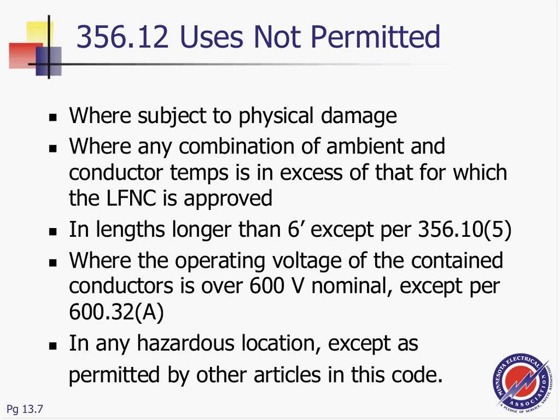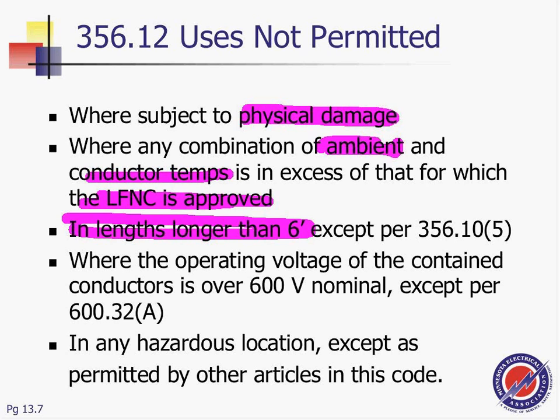Okay, now prohibition. Where can't I use it? Guys, severe physical damage. If you have physical damage, you might as well have rigid metal conduit installed. This is a non-metallic series. Ambient temperature shall not exceed what the conduit is approved for. So if the liquid flexible non-metallic conduit is rated for 90 degrees Celsius, you can't put a 250 degrees Celsius conductor in it because it defeats the purpose. It's not meant to be installed in lengths longer than 6 feet. There's an exception coming for that one.